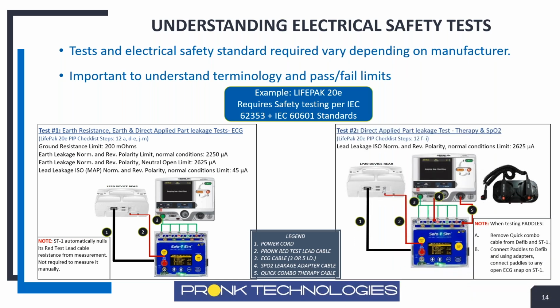Now, what's interesting about this device is they want you to do another series of tests. They refer to it as a direct applied part leakage test, but for the therapy and SpO2 cable. So the therapy cable also is an applied part, connected to the patient with the pads. And SpO2 is considered an applied part because you're putting a sensor on the finger. So they want you to test that separately.